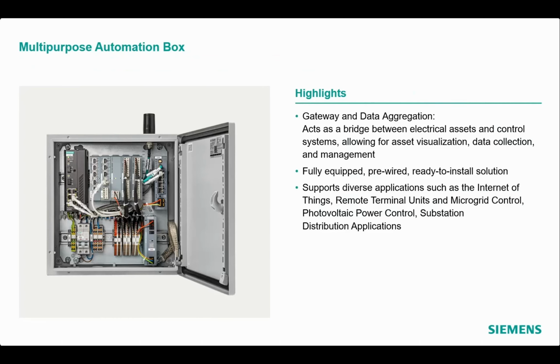If height restrictions in the compact substation do not allow the installation of the devices in the on-top mounted low voltage compartment, there is also the option to install the gateway, UPS, communication modem and other components into a separate multi-purpose and automation box. This box is available as a standardized product in our portfolio and can be ordered optionally besides the ring main unit and be connected via standardized interfaces to the switchgear. Installation can be done, dependent on the substation design, either in a separate control compartment or on the low voltage side.